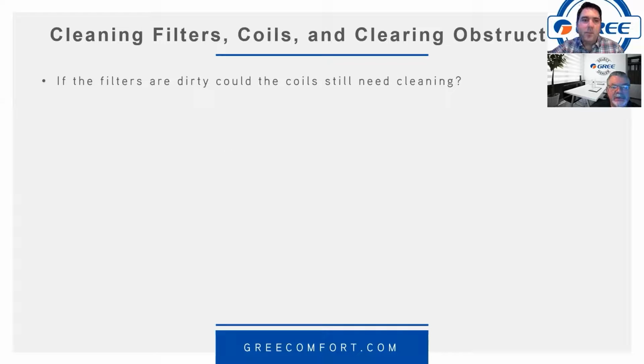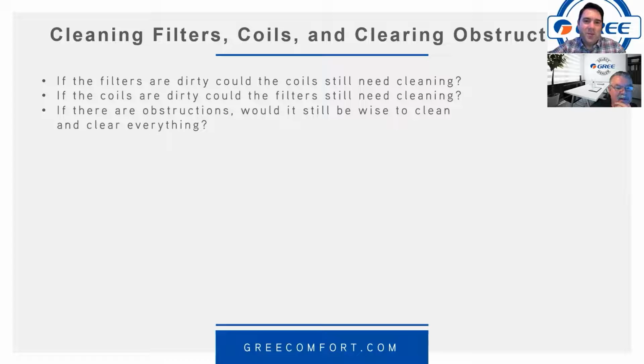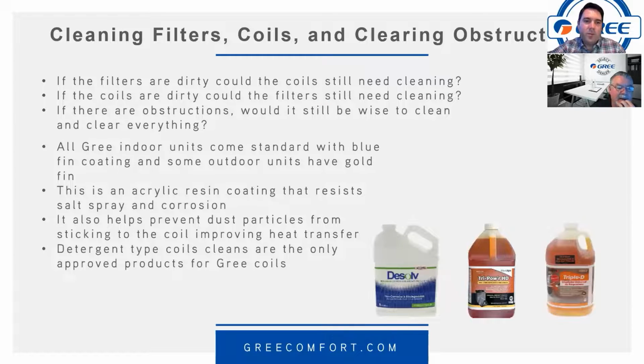So, cleaning filters and coils. If the filters are dirty, could the coils still need cleaning? Yes, very much so. And vice versa, right? If the coils are dirty, the filters could need cleaning. If there are obstructions, it would still be wise to clean and clear everything every time. One of the things to keep in mind is that all Gree units come with standard bluefin coating, and some of the outdoor units even have goldfin coating. It's an acrylic resin coating that resists salt spray and corrosion. It also helps with heat transfer and it helps to keep things from sticking to the metal.